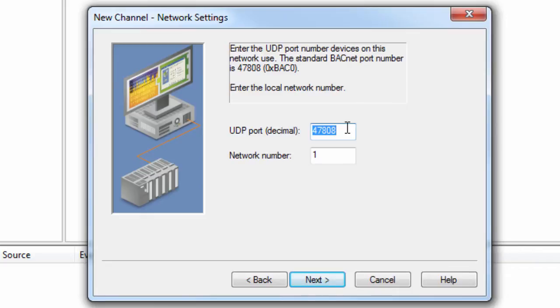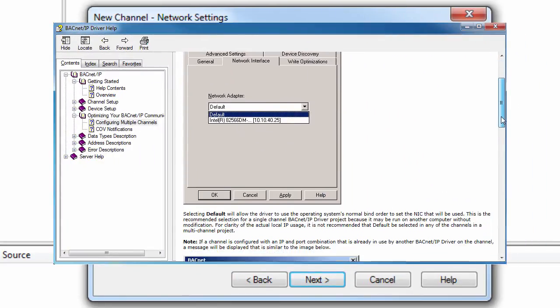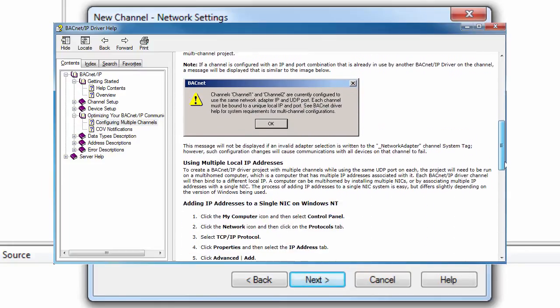However, unlike most Ethernet drivers for TopServer, the BACnet IP driver requires that each channel bind to a unique local address. The address is the combination of IP and port. To create a BACnet IP driver project with multiple channels while using the same UDP port on each, the driver will need to be run on a multi-homed computer. For more information on multi-homing, see the Configuring Multiple Channels section of the BACnet IP driver help file.